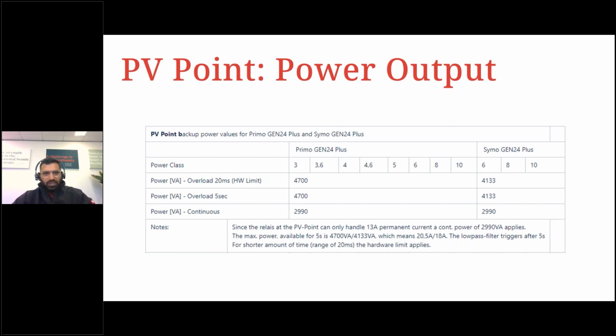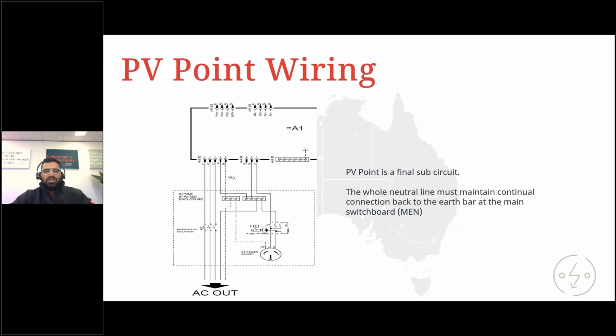So PV Point wiring. In Australia, PV Point is considered a final subcircuit, so it has to be RCD protected. The neutral line must maintain continual connection back to the main switchboard, and hence it is recommended to not use GPOs with inbuilt RCD and rather have them separate in an enclosure where you have a separate RCD and a separate power point.